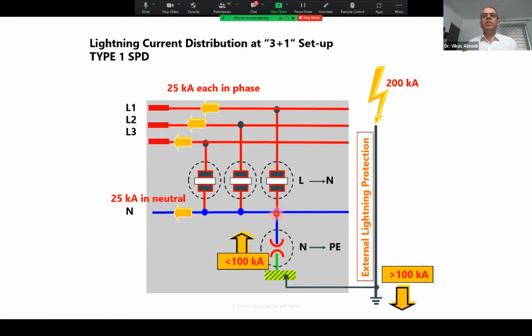And after that, this current will divide into 3 lines and neutral. That means divide by 4. So each line will have 25 kiloampere of current, and 25 kiloampere of current will flow through the neutral. So each arrestor that is used at the lines will not be 1/3, but 1/4 of the rating of the neutral to earth arrestor. So that is why you see that all the arrestor manufacturers are making line to neutral arrestors for the rating 25, 30 kiloampere, and the neutral to earth SPD is always for the higher capacity, which is 100 kiloampere. The thumb rule is divide by 4. Simple, because there are 4 lines.